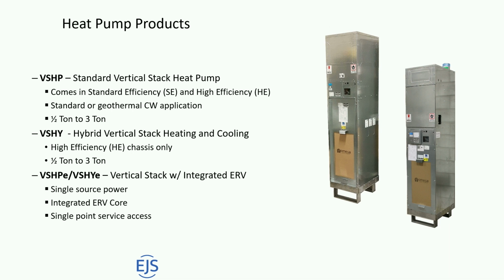This is different in the fact that a hybrid heat pump has a compressor for water-cooled cooling, but in heating mode, I'm actually going to get 100 to 105 degree water for the sole heating purpose. And so it's kind of a hybrid system. Compressors don't run in the heating mode. So that's a hybrid system. And you can use that in the geothermal application because you're still going to be rejecting heat to the ground during cooling mode, and in heating mode, you do need 100 to 105 degree water. 105 is kind of that magic temperature because you don't need to insulate below 105 degrees. So engineers are specifying 105 degree heating capacities.